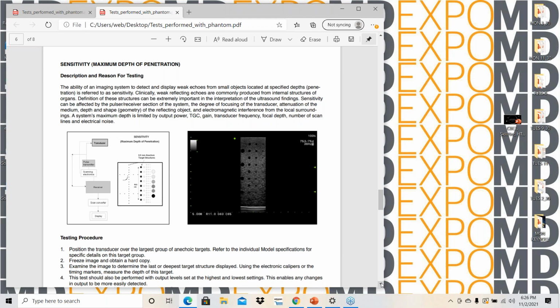And they call it low, medium, or high. So you have a low frequency range, a medium, and a high. This is a 3 to 12 megahertz probe. So you probably go at 3, you go at 12, or low, and then you split the difference at 7.5, and there you go. So you have to test at all those.